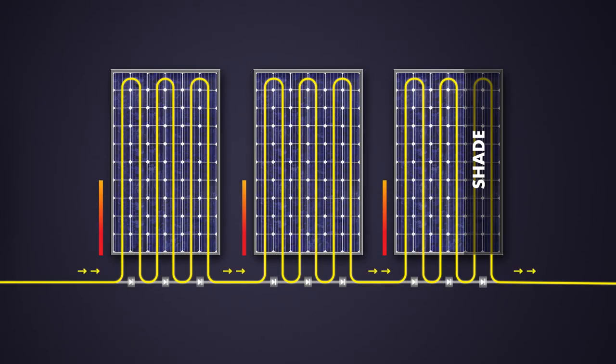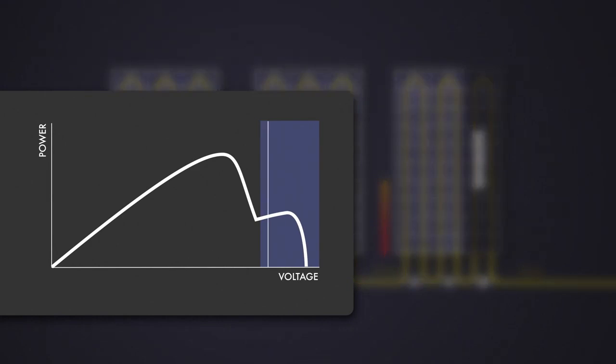In case of a partially shaded PV array, and when using classic MPP tracking, the current through all PV modules will be limited to the current of the shaded PV module. Due to its classic MPP tracking algorithm, the inverter chose the wrong MPP voltage at a low local maximum powerpoint. The bypass diodes are not active.